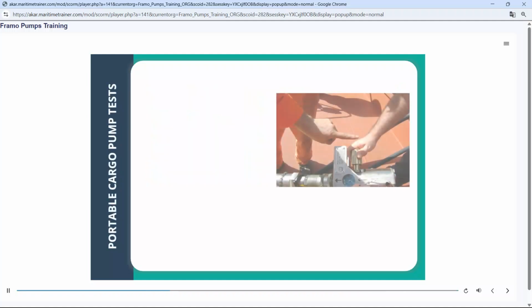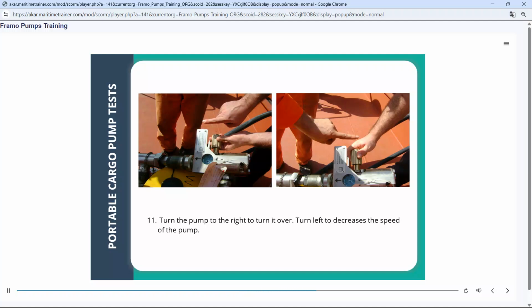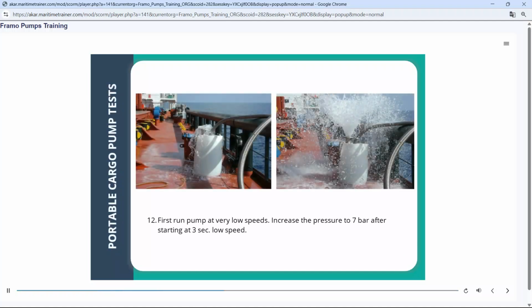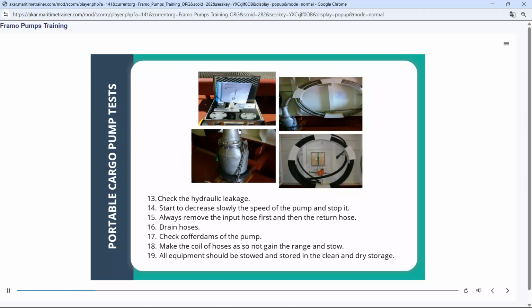Turn the pump to the right to turn it over. Turn left to decrease the speed of the pump. First run the pump at very low speeds. Increase the pressure to 7 bar after starting at 3 seconds low speed. Check the hydraulic leakage. Start to decrease slowly the speed of the pump and stop it.